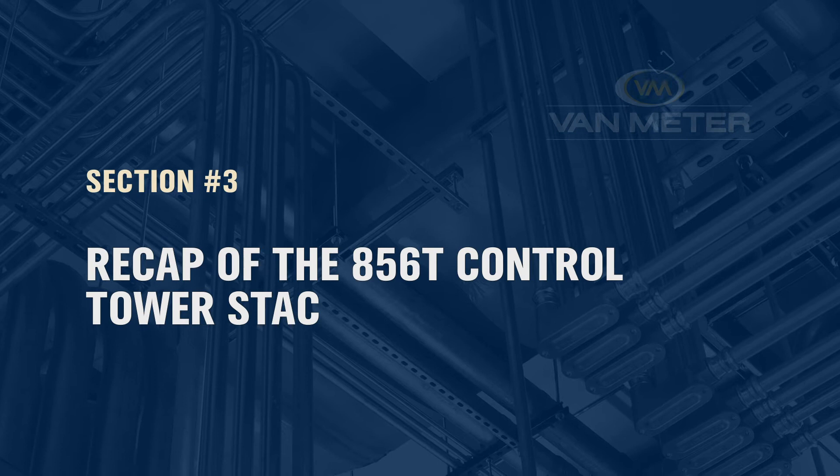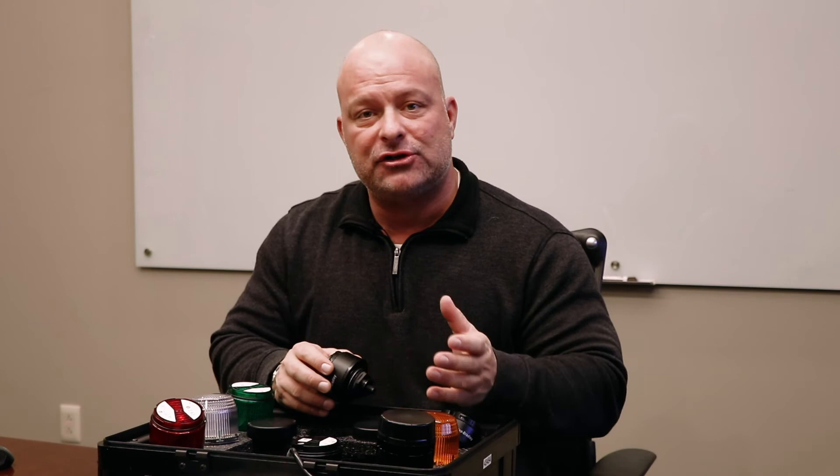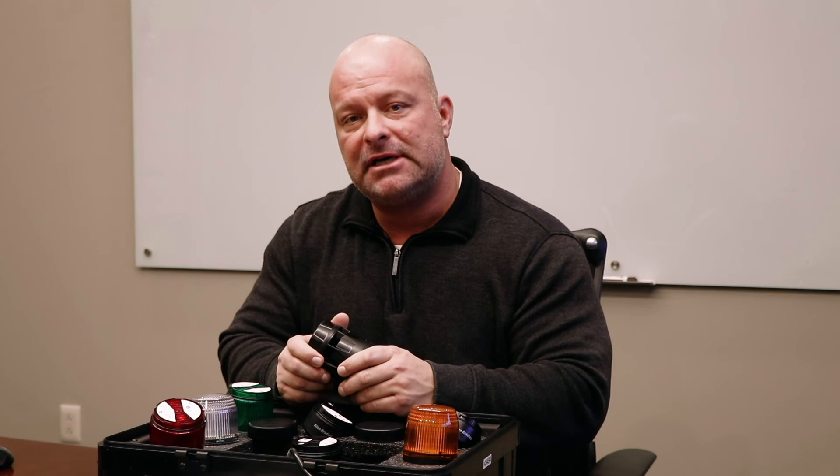To recap on the 856T control tower stack light: the stack light comes with two different power bases — 120/240 volt AC or 24 volt AC/DC. Having two different power bases means that all stack light modules are the same, which saves you SKUs in your crib and eliminates the need for extra modules. We have multi-function modules offering steady state LED, strobe, and different flash options, as well as transducer and piezoelectric sound modules. The transducer sound module offers up to seven different sounds off of seven circuits, giving you ultimate flexibility in annunciating what's going on with your machine.